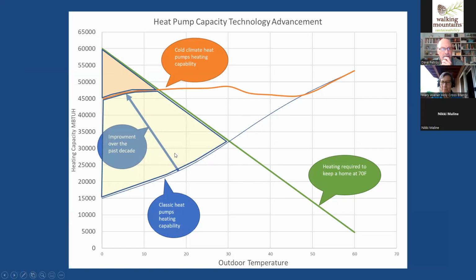Over time, engineers kept working on it, and now cold climate heat pumps are able to hold their capacity down to around 15 or 10 degrees, the crossover point. Now there's just a small wedge of heating needed from supplemental heat, a bit bigger out at colder temperatures. We'll talk about that in the next couple slides—that supplemental heat is either electric, or if paired with a furnace, a little gas or propane. So this is one big improvement: the ability to hold capacity and heat when it's really cold out.